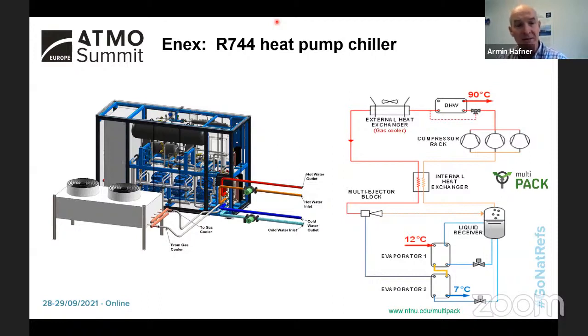But this heat pump chiller developed by Enex shows that it is possible to really outperform even existing HFC chillers, and we can provide a future-proof solution which is non-flammable, especially in the environment around hotels inside the city center, where it might sometimes be challenging to have a flammable refrigerant. We can even build very efficient chillers with propane, providing all the safety measures, but sometimes this might be a very good option, especially when you need very hot water. These systems can produce temperatures up to 90 degrees, or lift the water temperature from 10 degrees to 90 degrees in one unit, which then reduces the number of storage devices you need for hotels and so on. It's a very good product, and this will enter more and more of the marketplace.